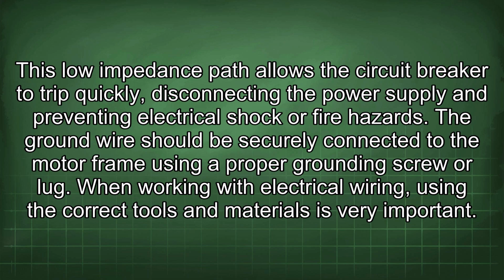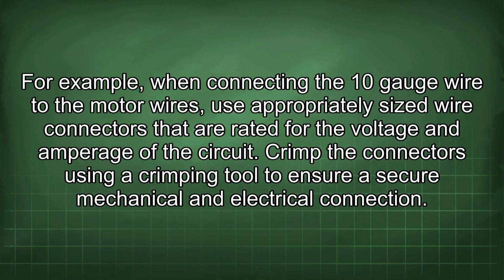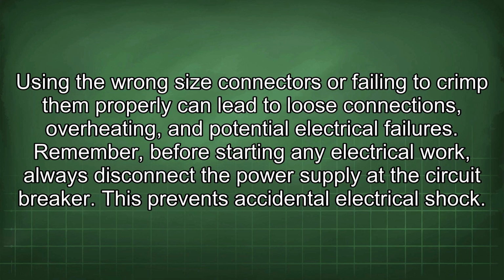When working with electrical wiring, using the correct tools and materials is very important. For example, when connecting the 10-gauge wire to the motor wires, use appropriately sized wire connectors that are rated for the voltage and amperage of the circuit. Crimp the connectors using a crimping tool to ensure secure mechanical and electrical connection. Using the wrong size connectors or failing to crimp them properly can lead to loose connections, overheating, and potential electrical failures.